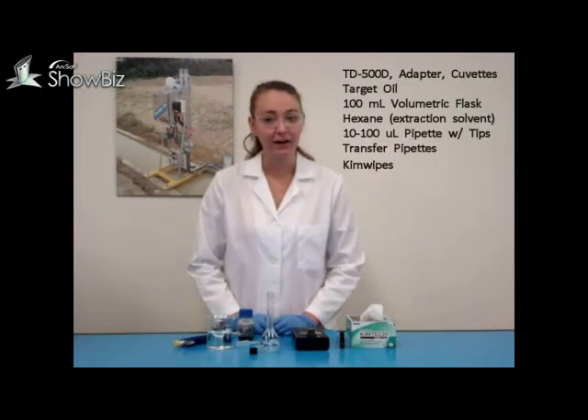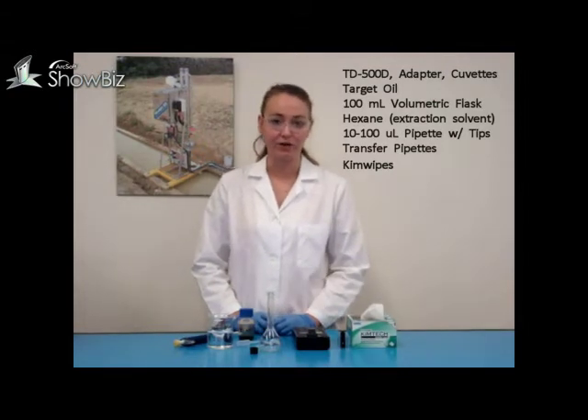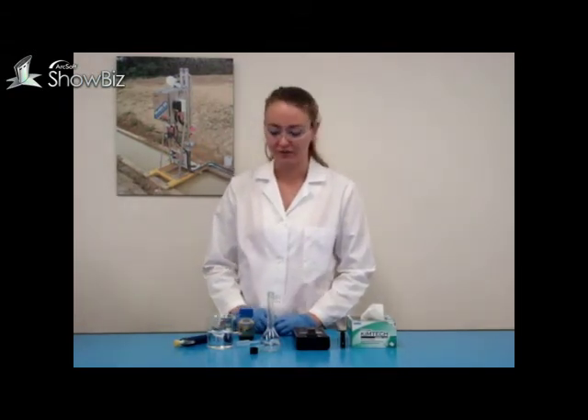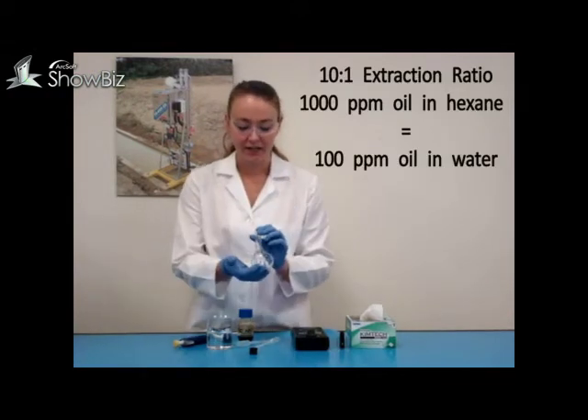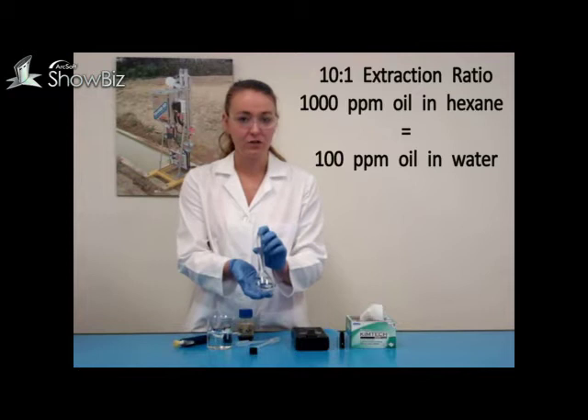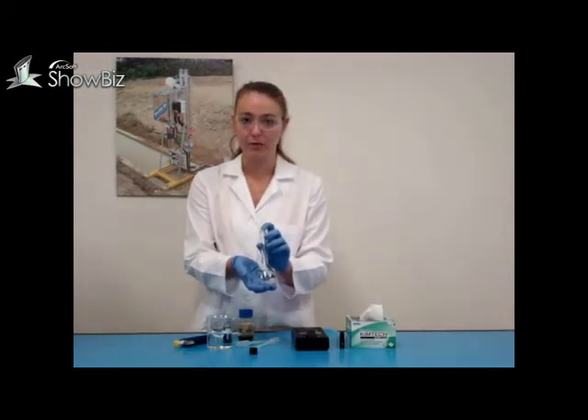Hello, today we will be preparing calibration solutions for the TD-500D oil and water monitor using solvent extraction. You will need to prepare a calibration standard solution. We will be preparing 1000 ppm oil in hexane, which is equal to 100 ppm oil in water.